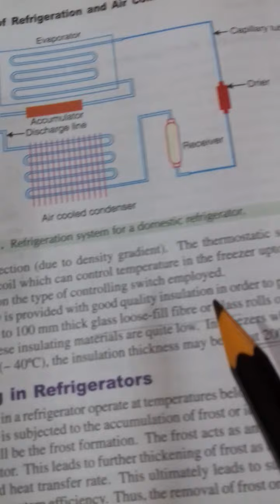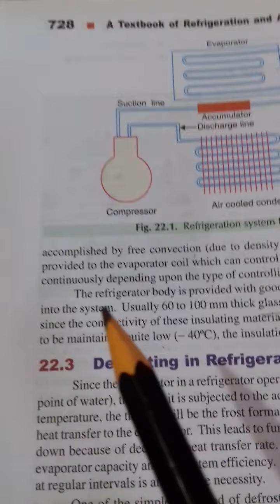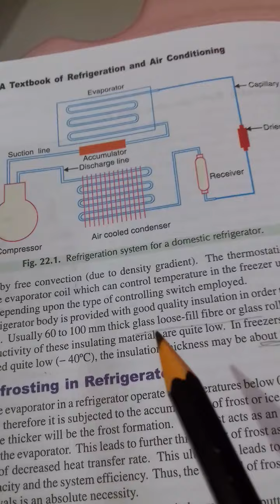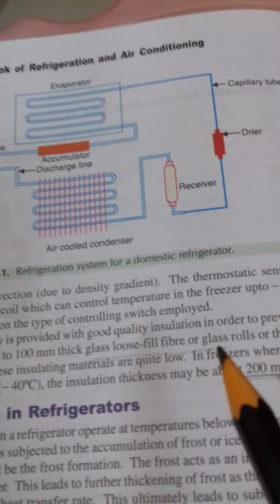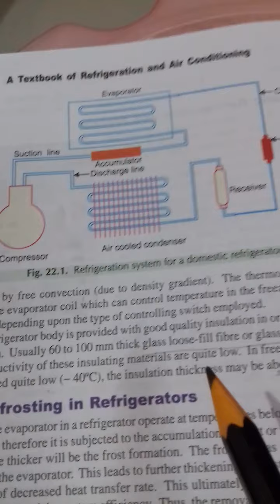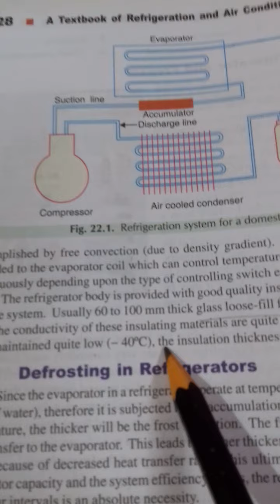The refrigerator body is provided with good quality insulation in order to prevent heat transfer into the system. Usually 60 to 100 mm thick loose fill fiber or glass roll or thermocol is used, since the conductivity of these insulating materials is quite low. In freezers where the temperature has to be maintained at quite low, minus 40 degrees centigrade, the insulation thickness may be about 200 mm.